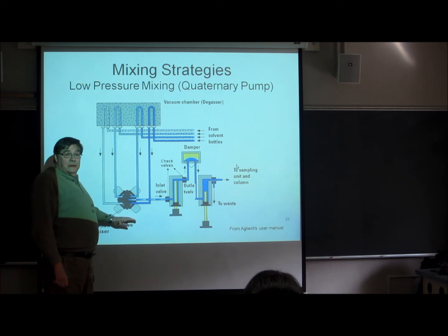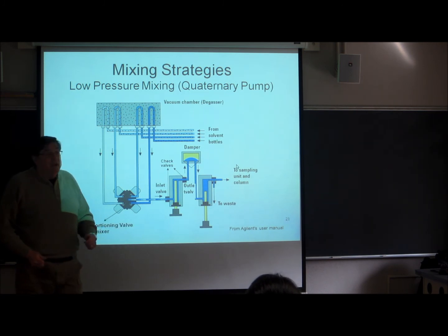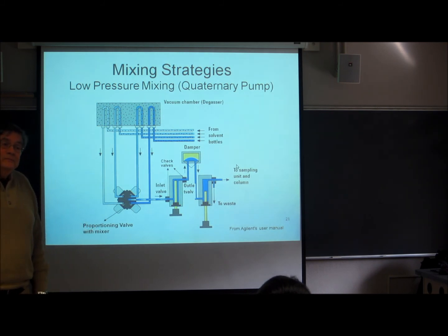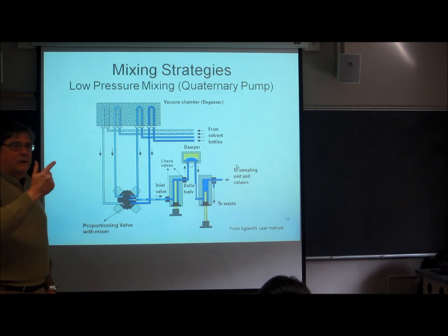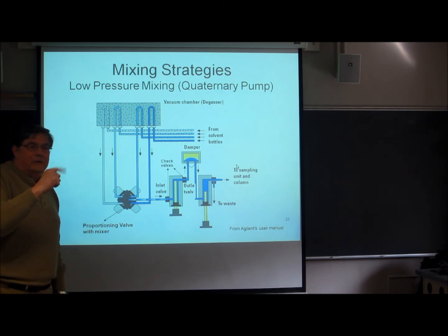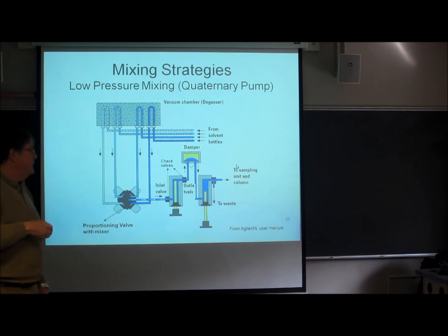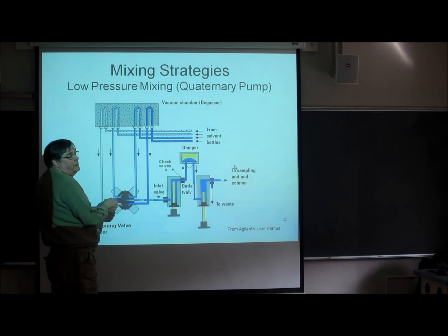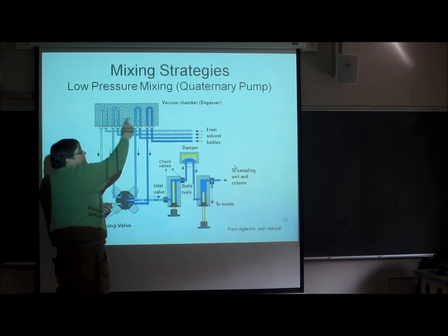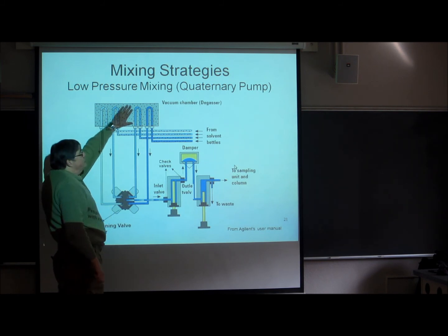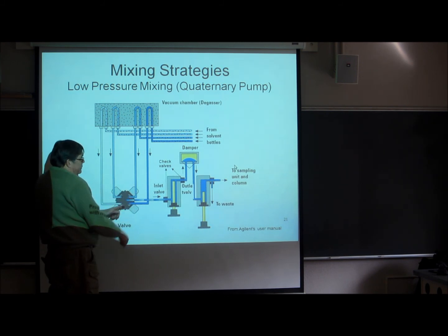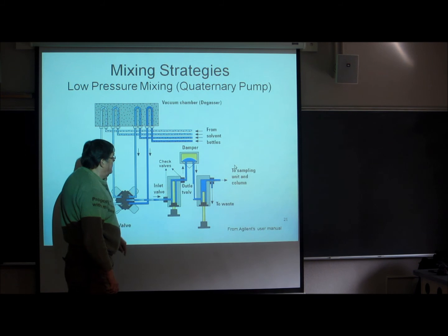And if the organic material has a lot of air in it, the water will cause the air to evacuate and form bubbles. Those bubbles are bad. I don't think I showed you in the check valve, but bubbles in a check valve make them stutter. And that produces a change in the flow and interferes. Bringing in solvents that will provide different solubilities for gas, and that's what this evacuator is about.